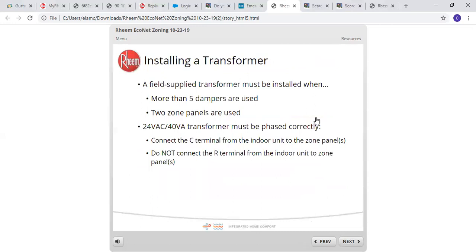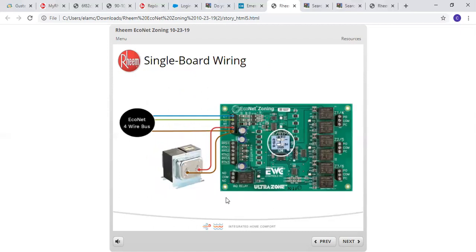In some instances, you will have to install a secondary transformer. Field supplied transformer may be installed when more than 5 dampers are used or 2 zone panels are used. The 24 volt 40 VA transformer must be phased correctly. Connect the C terminal from the indoor unit to the zone panel, and do not connect the R terminal from the indoor unit to the zone panel. That is important. And I'll show you how that's set up here.